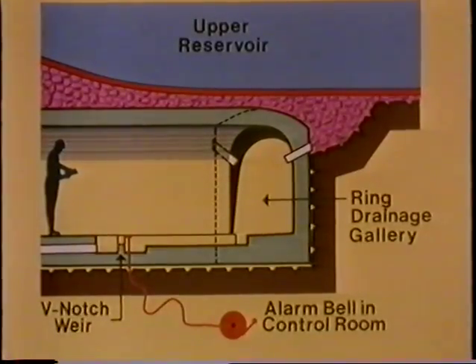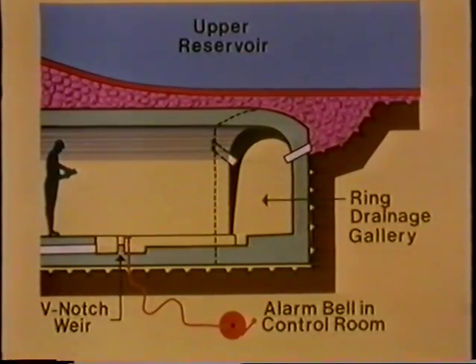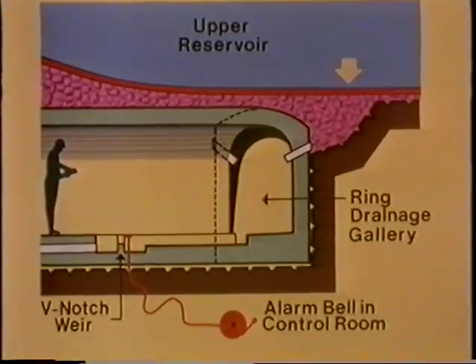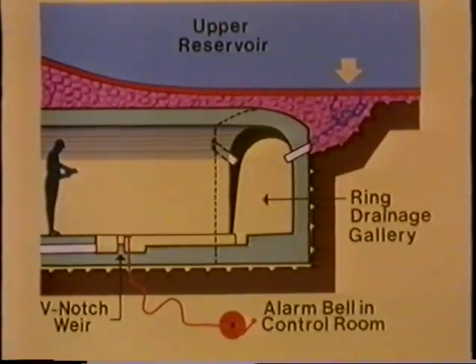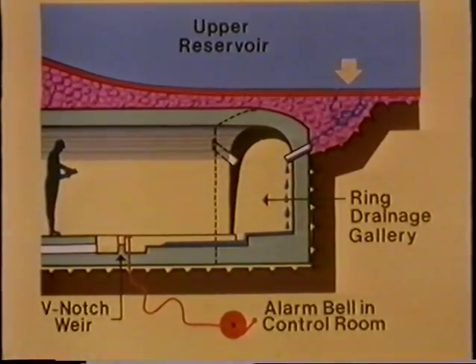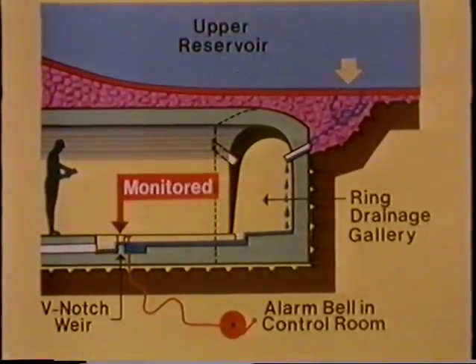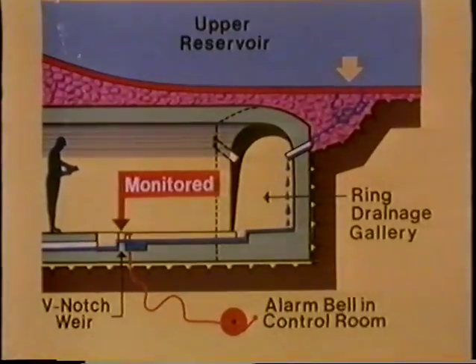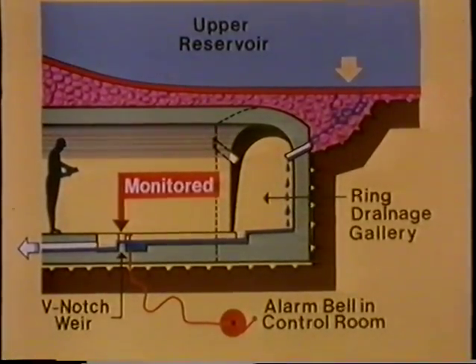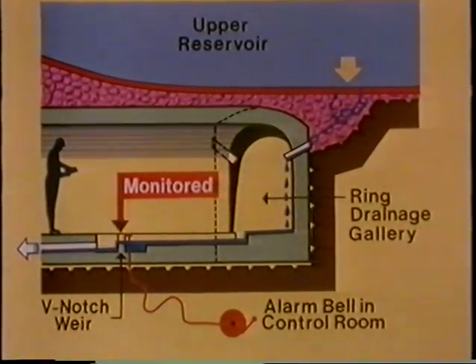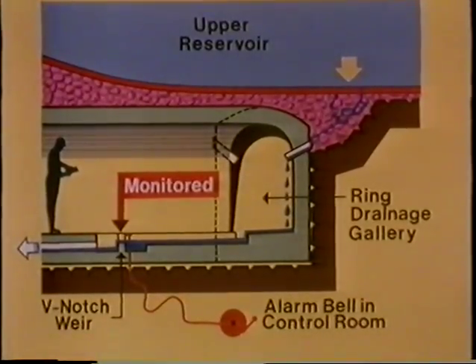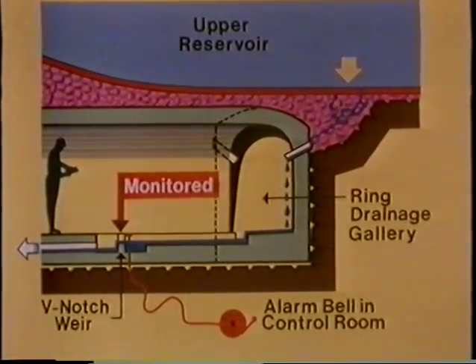A drainage gallery sump collects coolant and water seeping into the cavern, from which 3 to 5 pumps discharge it into the lake. A backup system is provided by the flood level monitoring equipment, which will operate controls automatically in emergency conditions in order to start up the pumps, close the flap gates and the spherical valves, isolate the main electrical network, and start up the standby diesel generator.